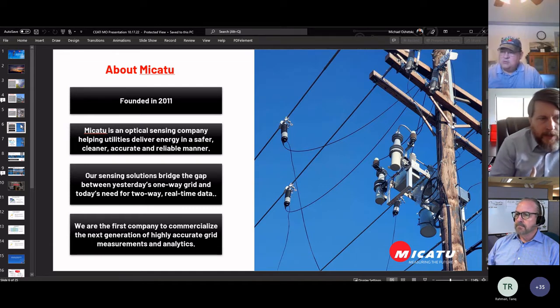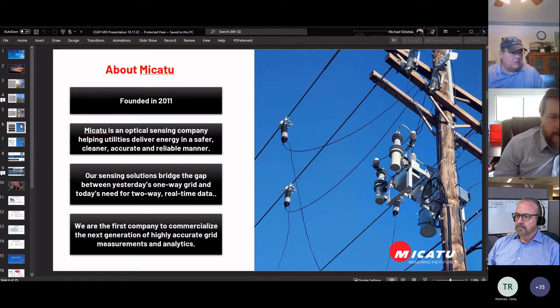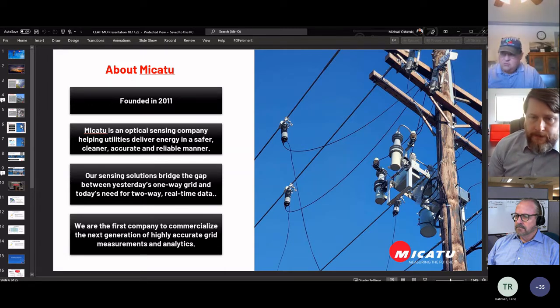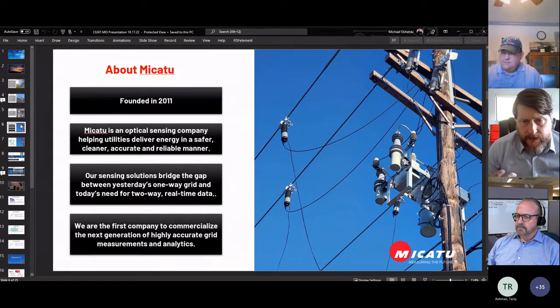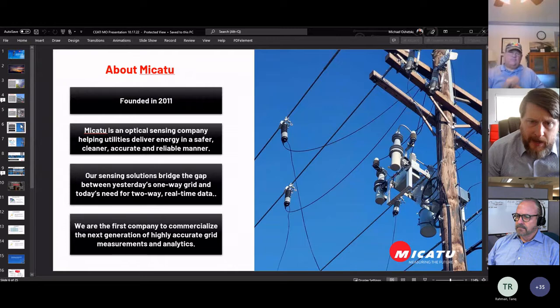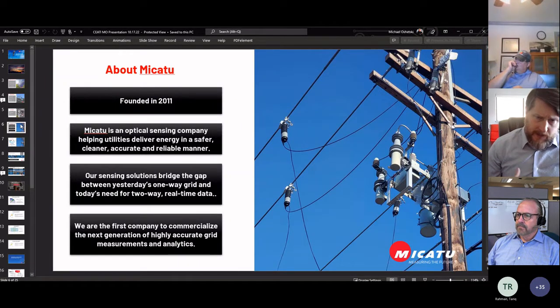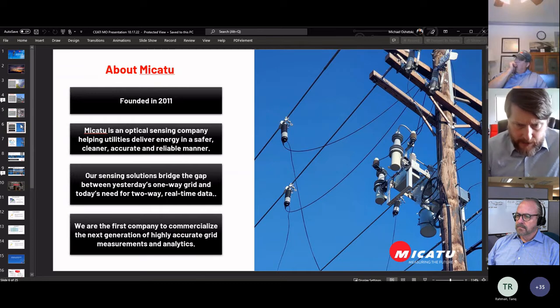Some beneficial attributes of optical sensing: you're isolated from your measurement. That means high transients and fault conditions don't translate down to the pole or the measurement device, giving a higher level of safety. We're also not a source of sparking or fire. Being isolated from this gives us a lot of important attributes.